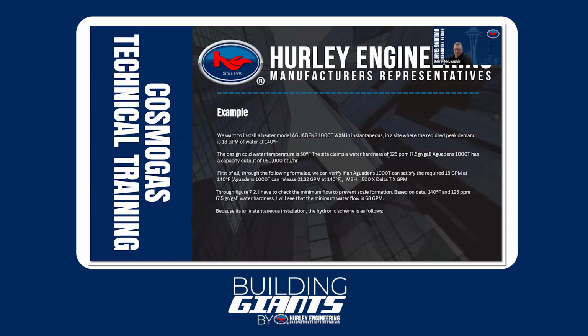So there's a little bit more to it. That gives you a baseline of where you would start, but we have to account for other items as well. So we'll do an example. We'll start from what information you're likely to have on site and what you would do with that. Let's say we go on site and they know their demand is 18 gallons per minute. Maybe you've done a fixture count, or it's just one item, or some kind of washing or laundry equipment. But you know you have 18 gallons of demand at 140 degrees.